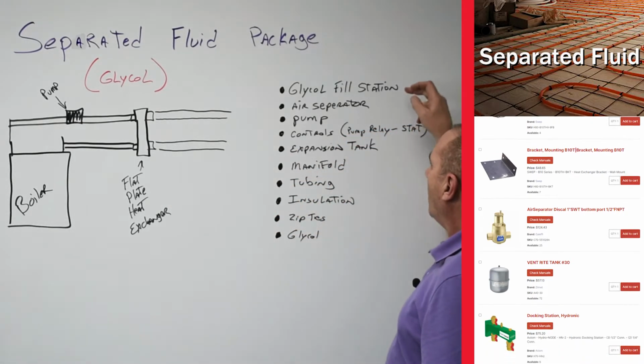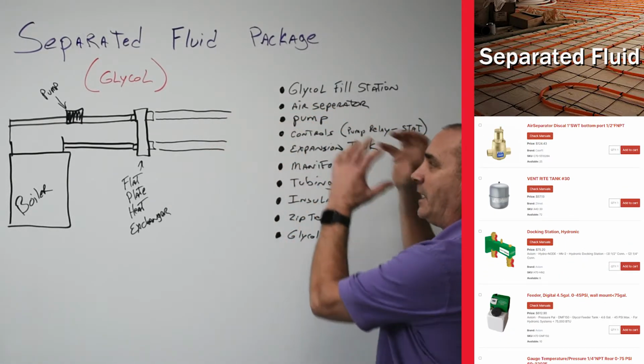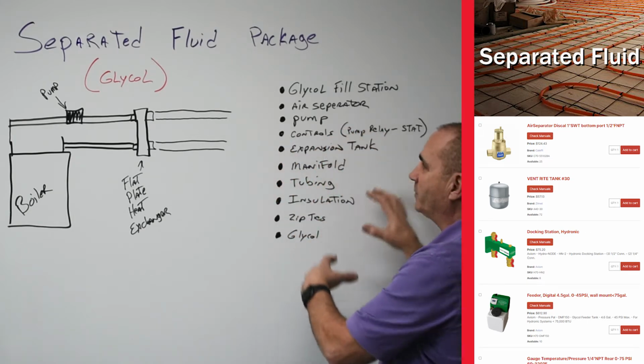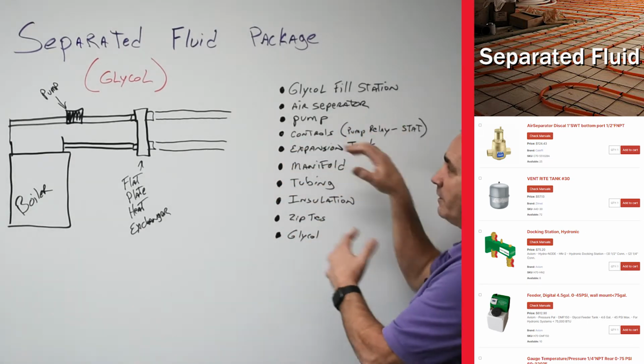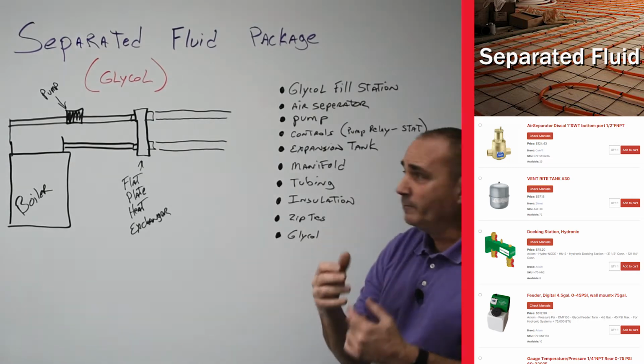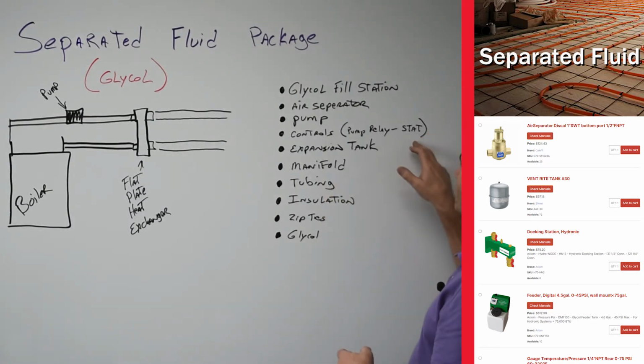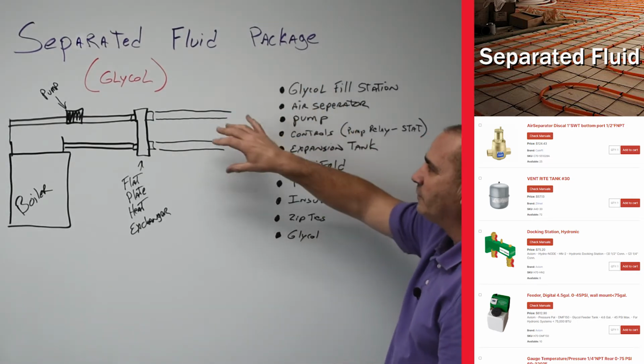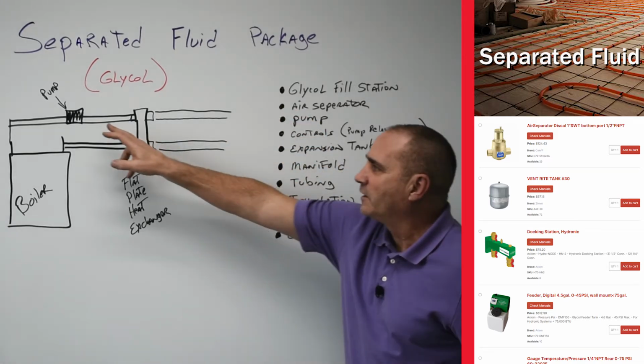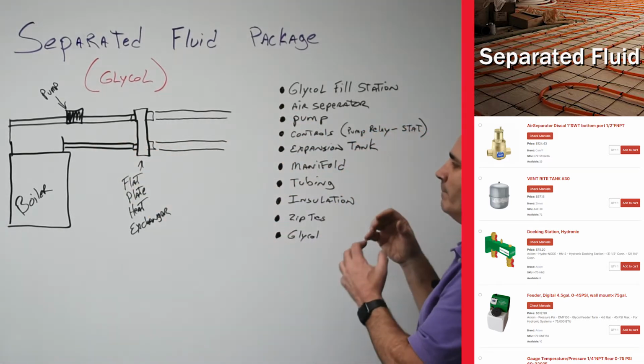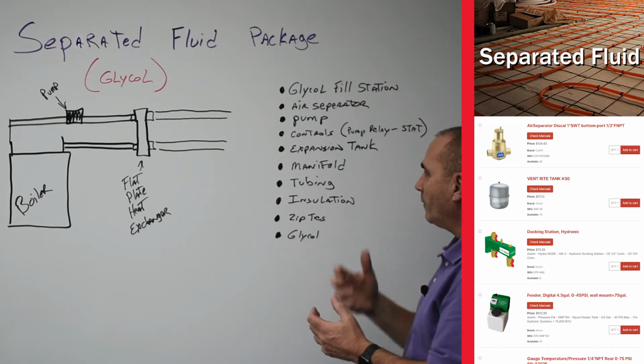You're going to need a glycol fill station to keep pressure on it and fill the system. You're going to need an air separator on this side, a pump or pumps depending on how big it is, controls, a pump relay to start the pump pumping, and a control thermostat.